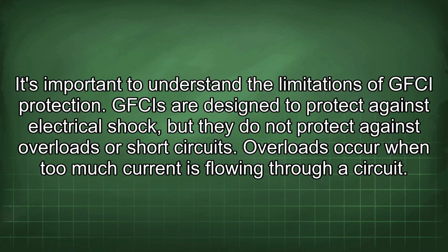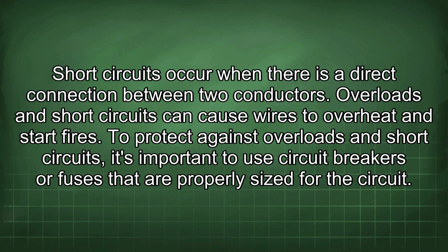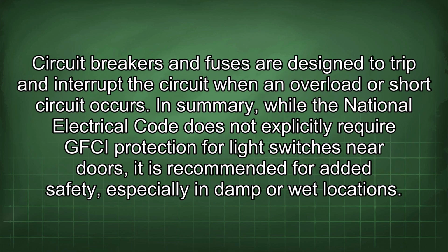It's important to understand the limitations of GFCI protection. GFCIs are designed to protect against electrical shock, but they do not protect against overloads or short circuits. Overloads occur when too much current is flowing through a circuit. Short circuits occur when there is a direct connection between two conductors. Overloads and short circuits can cause wires to overheat and start fires. To protect against overloads and short circuits, it's important to use circuit breakers or fuses that are properly sized for the circuit. Circuit breakers and fuses are designed to trip and interrupt the circuit when an overload or short circuit occurs.